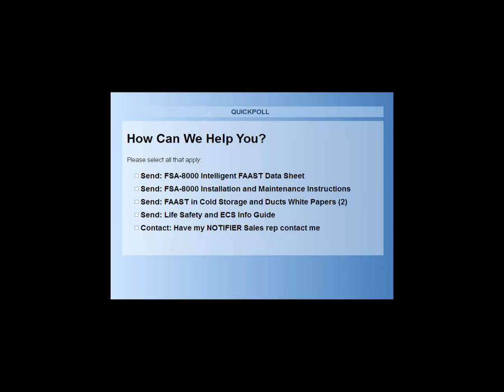Okay. A couple piping questions here. Can pipe be painted? That's a good question, David. The final decision on pipe painting generally comes down to the AHJ. I believe for the CPVC pipe that we offer through System Sensor, Harvell says that it may be painted with water-based paint. Again, the final decision is going to come down to the AHJ. If your AHJ is okay with the pipe being painted, we recommend painting the pipe before you drill the holes, so that no holes are painted over and subsequently blocked. Also, there are still labeling requirements where you would need to place stickers on the pipe to indicate that it is a smoke detection apparatus.